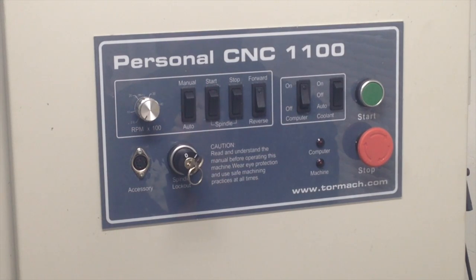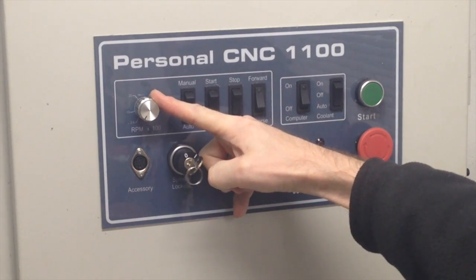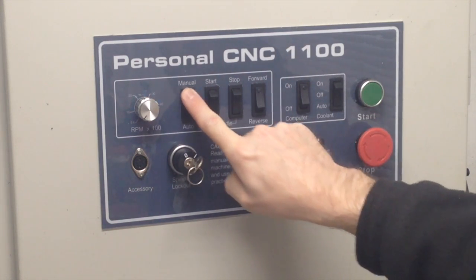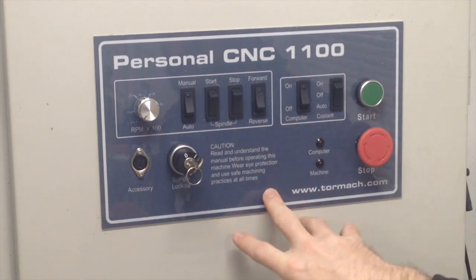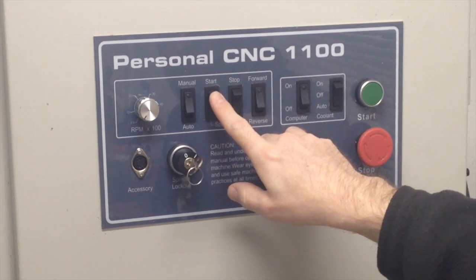All right, during this process, you're going to need to power cycle the VFD, and that's controlled via a solenoid in the control cabinet. So the easiest way I've found to do this is to set the speed control to minimum, put it into manual mode, and then when you want to turn power onto the VFD, hit the start button.